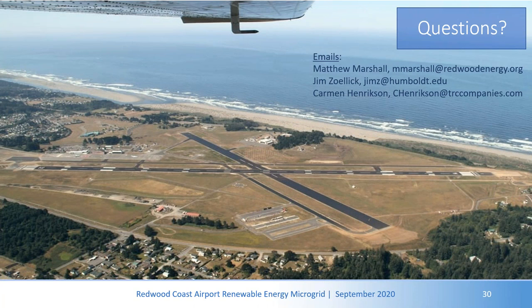The DC coupled solar plus battery system will be managed such that if there's too much PV power, it will just be curtailed by the control system. In order to manage the battery state of charge, we don't want to overcharge the battery. And if there's not enough and the battery state of charge goes too low, eventually we would just shut down.